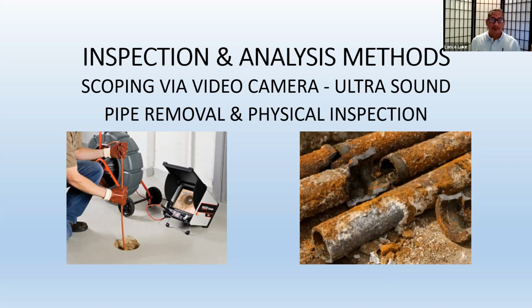The best method is to actually go in and remove the pipe and do a physical inspection. Okay, that's where it's undeniable that it's a problem, because sometimes we have to gather all the information, and there's unit owners in a condo who say, well, we don't think that our pipe's bad. I never had a leak. But then when we present the actual samples and say, look, here's the corroded pipe, here's a cracked pipe. And they're going to say, well, yeah, but that came from one of your other projects, not our building. And I said, no, this came from your building. We did testing and took out sections of pipe.